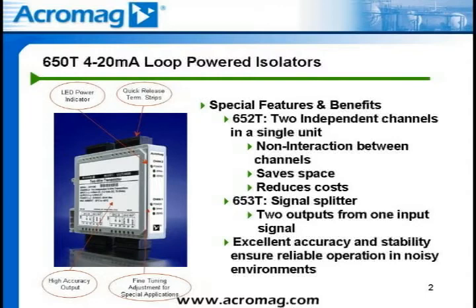This module fits applications where two devices need the same analog input signal but need to be isolated. One example would be where a 4 to 20 milliamp DC signal is used as an input to both a PLC and a DCS input card. Both provide 24 volts DC to power their respective analog input loops, and the ground potential for the PLC and DCS may also be different, so the input to each of the analog input cards needs to be isolated.